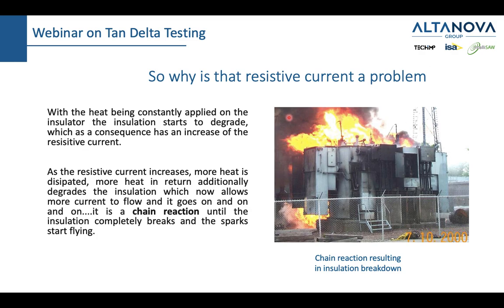So with the heat being applied constantly on the insulator, the insulation starts to degrade, which as a consequence has an increase of the resistive current. As the resistive current increases, more heat is dissipated. More heat in return additionally degrades the insulation, which now allows more resistive current to flow, and it goes on and on and on, and it's a vicious circle. It's a chain reaction which, if not stopped at the right moment, will cause something like this. So hopefully that will not happen.